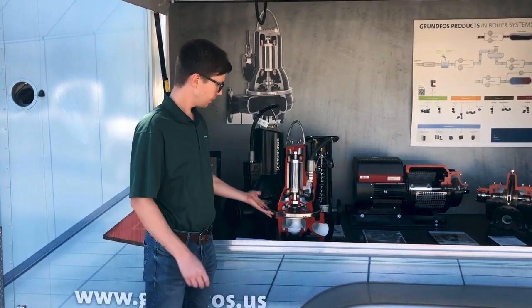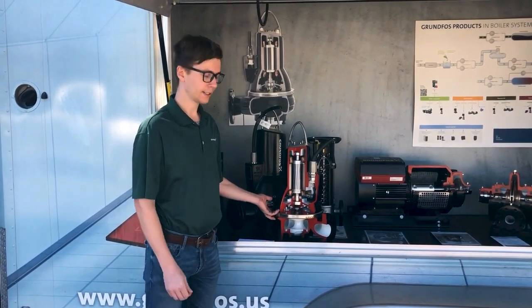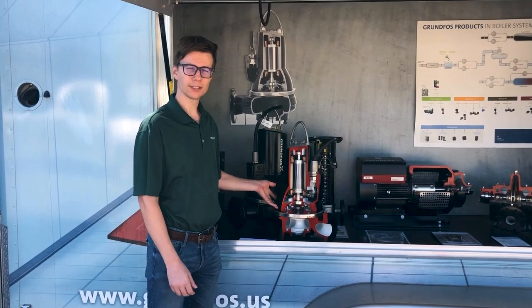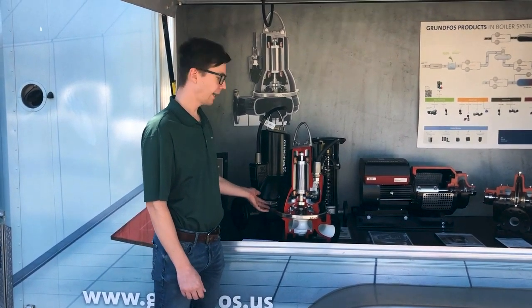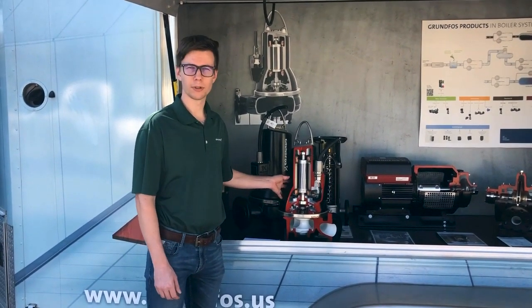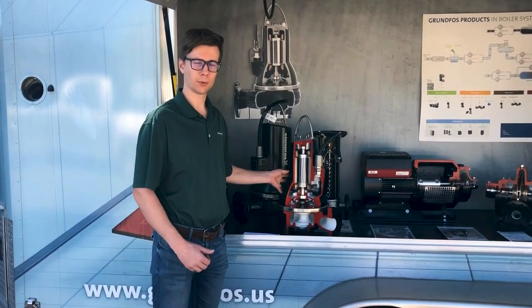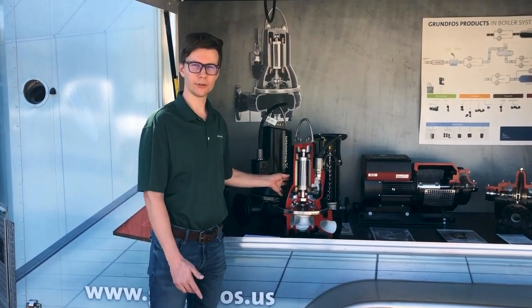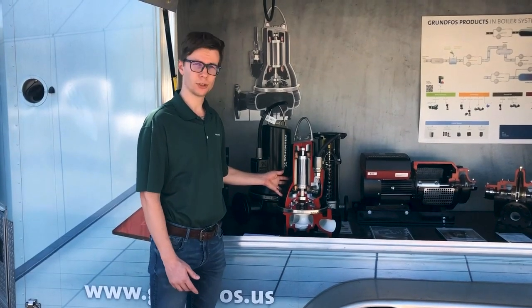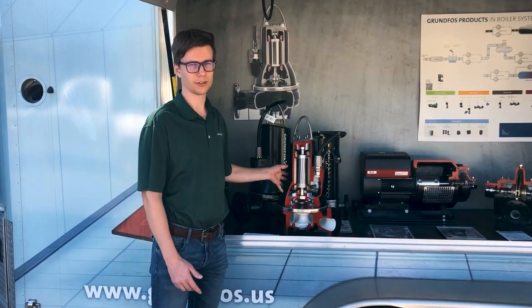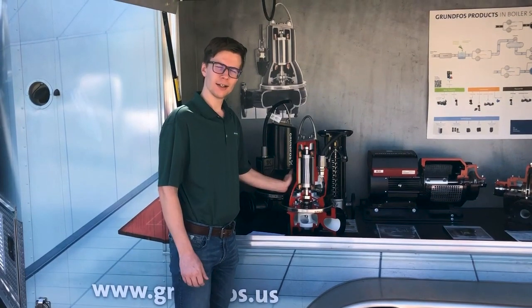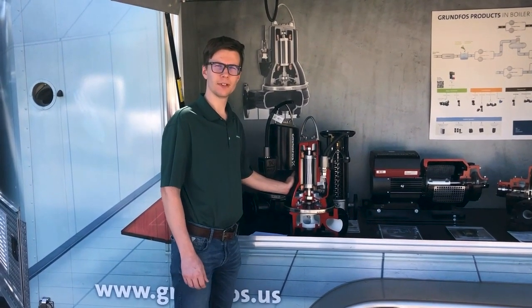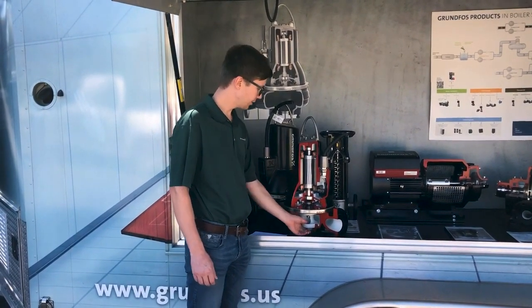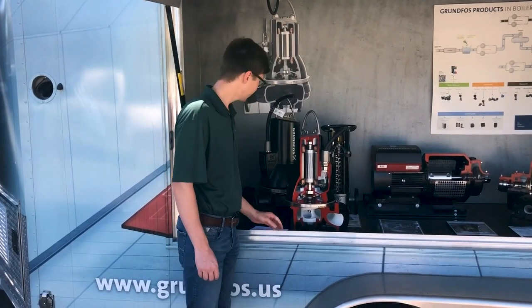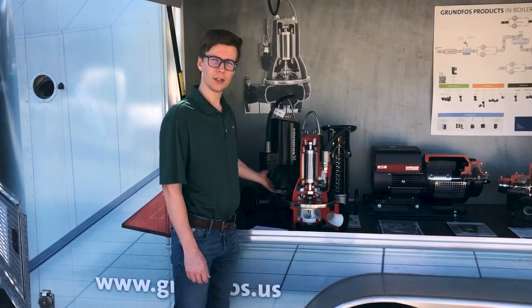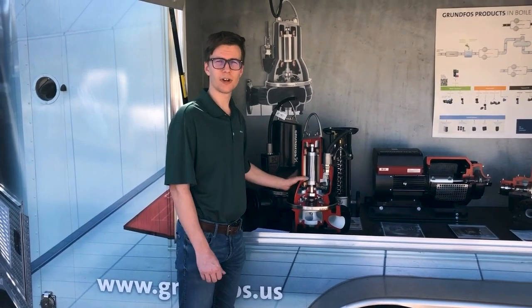Small SL pumps are available in 2.5, 3, 4, and 6-inch discharge sizes, and 1.5 to 15 horsepower motors. The motors are explosion-proof, FM rated, inverter duty, and available in 3-phase, 208, 230, or 460 volts. SL pumps come with two different impeller options. We got the Grundfos S-tube that we have on this pump here, as well as vortex impellers for applications where raggy and long fibers might be a problem.